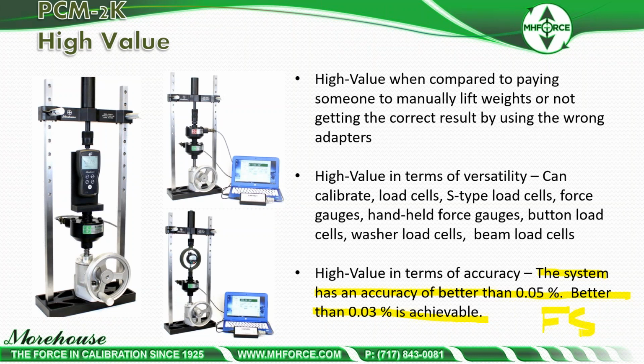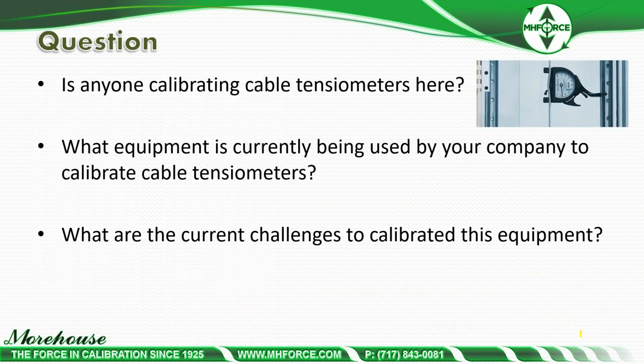And be wary of people that tell you accuracies of 0.0005 of full scale, 0.001 of full scale, because what does that mean? And be wary of what that means at the 10% point, because it does not always scale linear. In fact, my example is good. If we had 0.003 at capacity, and I'm saying 0.03 at 20%, that's not linear. 0.03 at 10% would be linear. So that's really where it is.